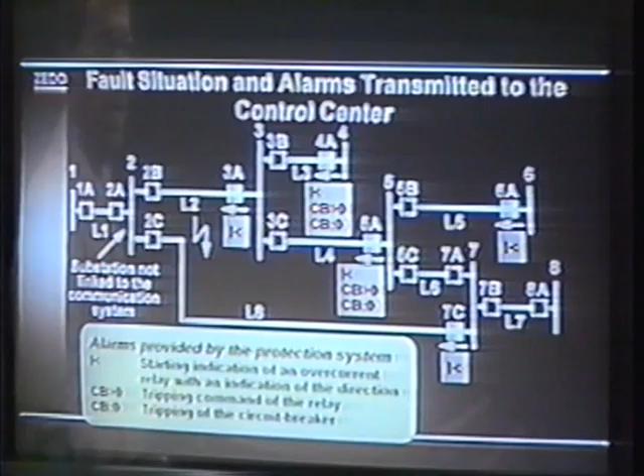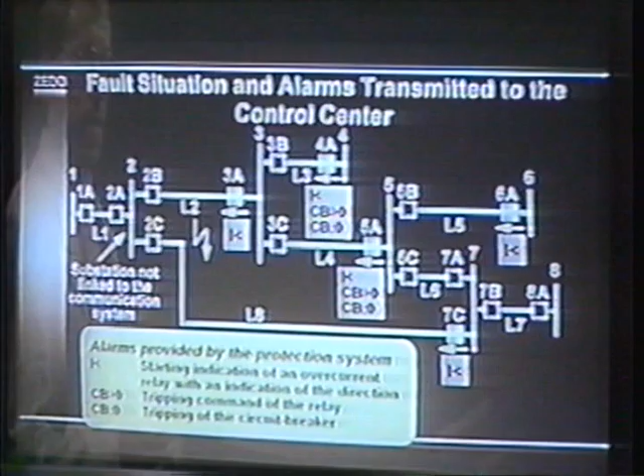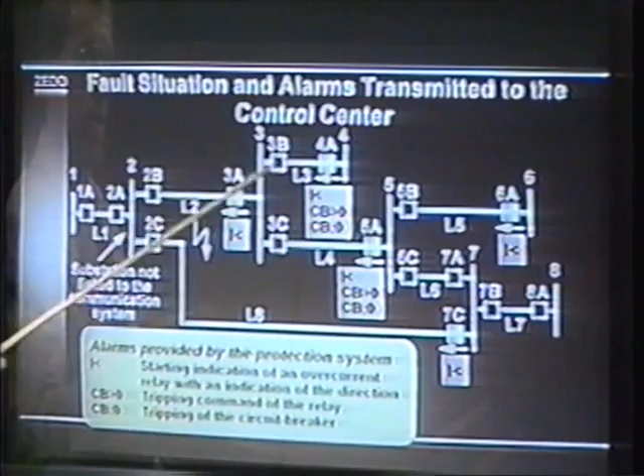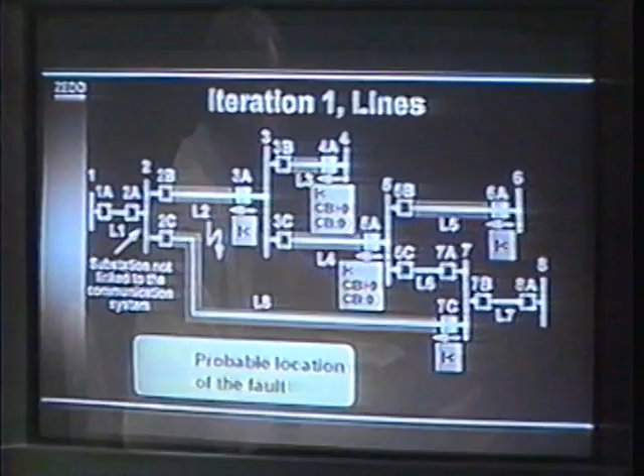In the first part of the first iteration, the diagnoses are done for the devices, the lines. The device-specific artificial neural network trained for fault diagnosis for lines is provided with the related input data for each line and does a diagnosis for all lines. The next slide shows the intermediate results, and we can see that, for example, line 5 is called a probable location of the fault because at the beginning of line 5, an overcurrent has been detected, so it's possible that the fault is on line L5. The same with lines 3 and 4.